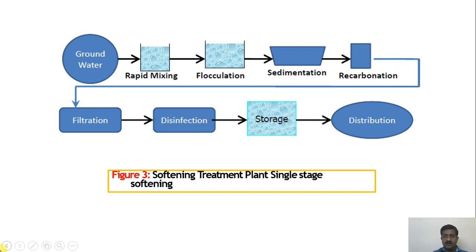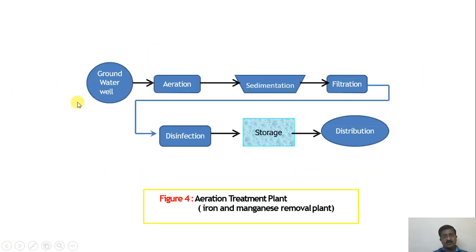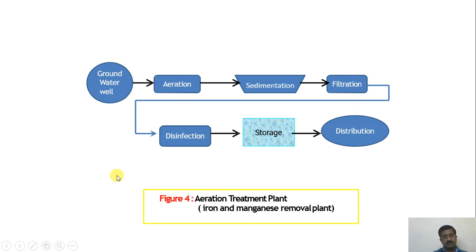Depending on which water source is used, the units in the flow diagram change accordingly. For a groundwater well used in a potable water treatment plant, the sequence is: aeration, sedimentation, filtration, disinfection, storage, and distribution. Aeration is sometimes provided very effectively to remove iron and manganese from the water source.